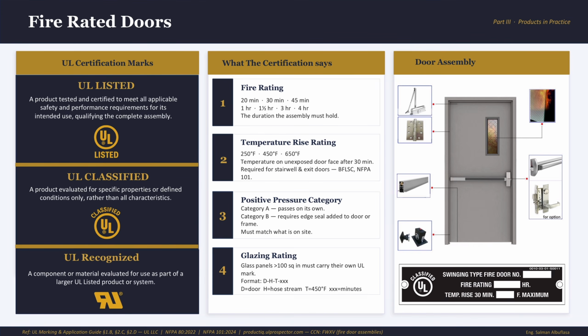And number 2, temperature rise rating. It's how hot the protected side gets after 30 minutes, as we can see right here. And this is critical for stairwells, because a door that can stop flames but conducts extreme heat through that escape route hasn't protected anyone. It just made that exit stairwell an oven and turned it into a heat trap.